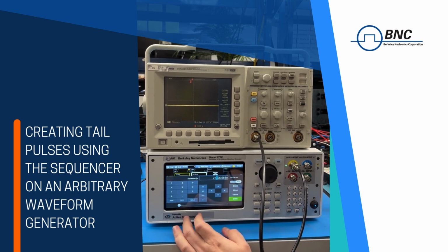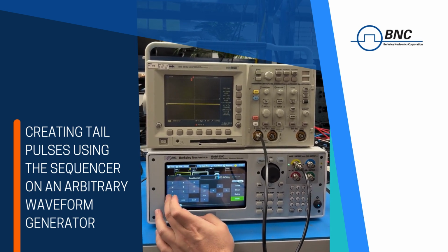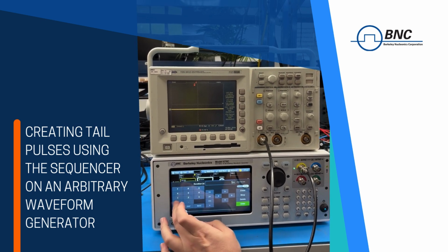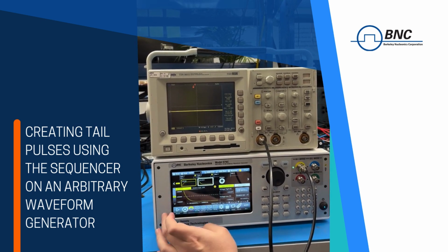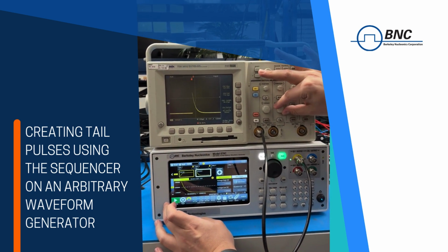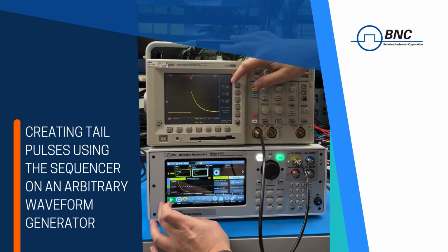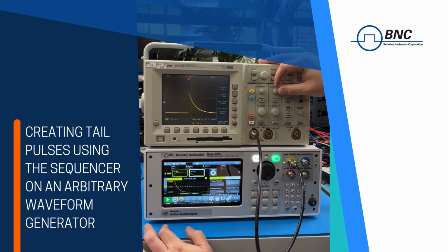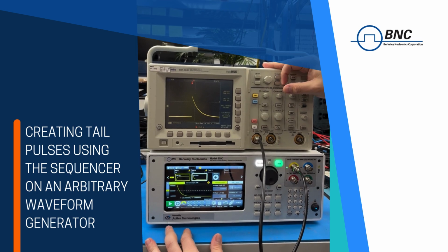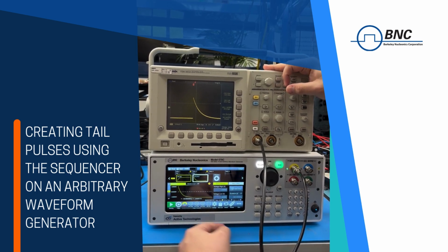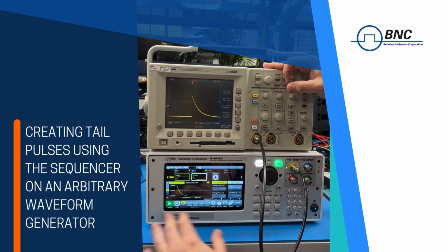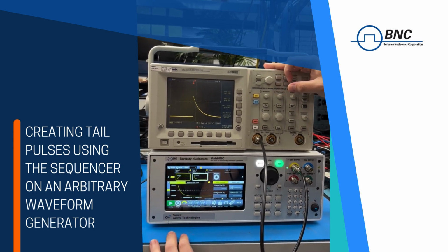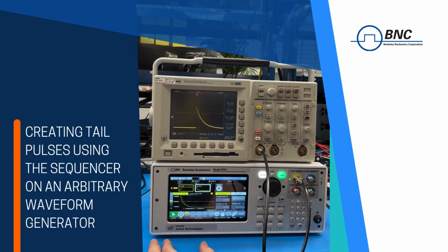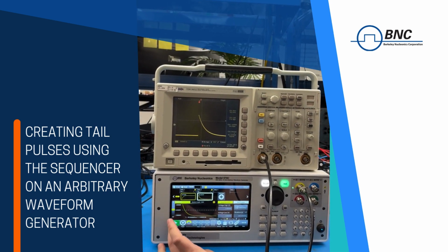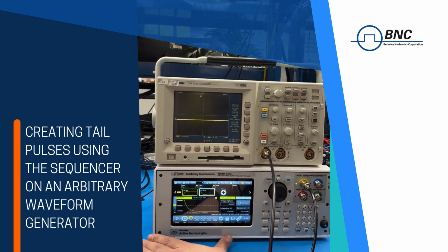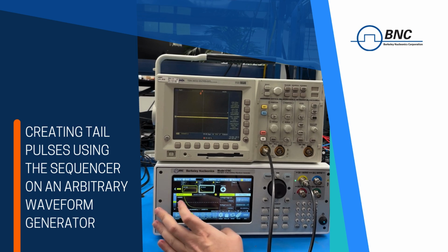So here I'm going to say I want a 100 microsecond fall time. I'm going to set this to, let's say, 500 micro. And what does that get us here? It gives me a roughly 100-ish microsecond fall time. You have to play with that a little bit because it is an arbitrary waveform generator. We're dealing more with how many points and how long a waveform is going, as opposed to the frequency like you would with a pulse generator or a dedicated delay generator. So that's one of the many ways that you can generate a tail pulse on this unit.